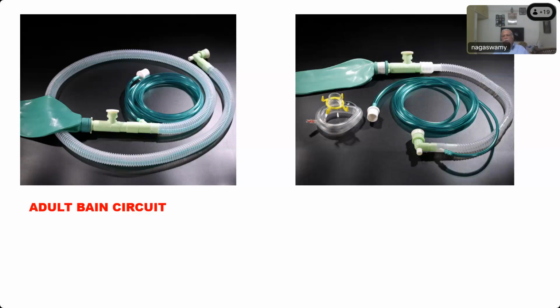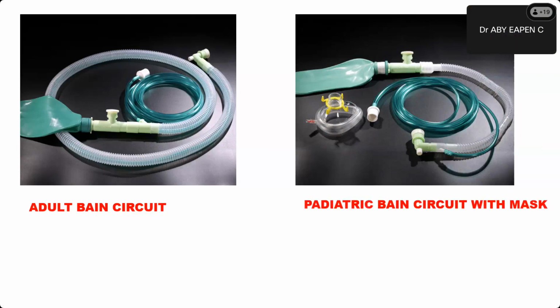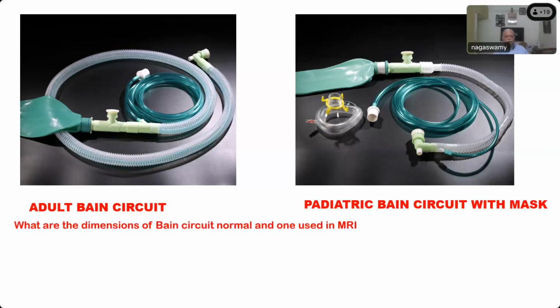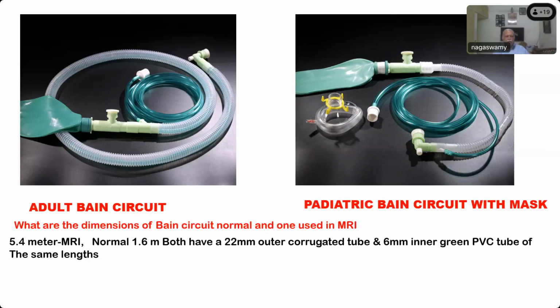What is this? Looking more similar to that. This green one is also a Bain circuit. Pediatric Bain circuit. Yes. Pediatric also has a smaller distance, you can see the shorter distance. So what are the dimensions? Again, 5.4 meters in MRI, normal 1.6 to 1.8 meters, with a 22 mm outer corrugated tube and a 6 mm inner green PVC tube of the same length. So the inner green PVC tube is the inspiratory limb, or delivery of fresh gas flow.